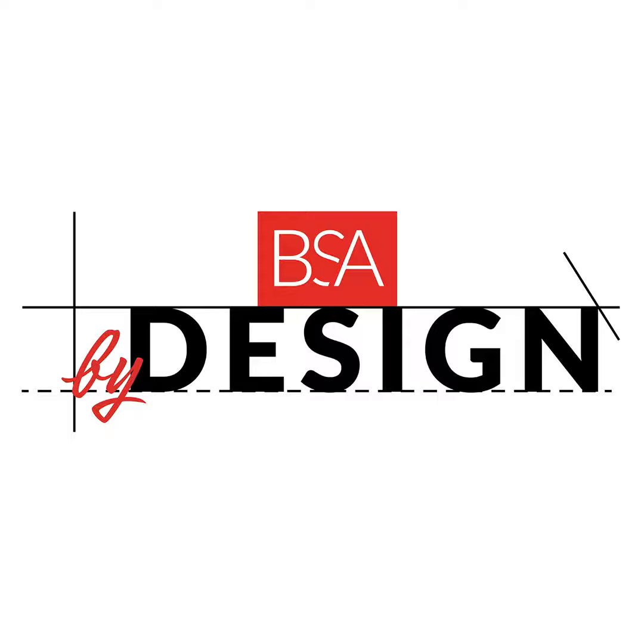I don't know what you guys design for a middle-of-summer design day, but we're at 95 degrees, 80% RH, and sometimes it's even worse than that. It can be middle of summer, cloudy, I'm at part load, then it rains and the sun comes out in 5 minutes. My outside air intake is on a roof, so now it's 100-plus degrees and very high RH right at my intake. So design day at 95/80 may be worse than that sometimes, but especially on high outside air percentage units, it's just a lot of energy to get all that down. It wrings a lot of water out of your system, a lot of energy.